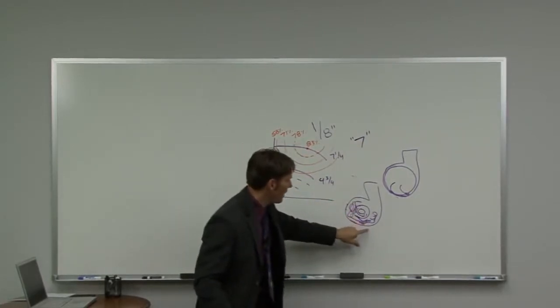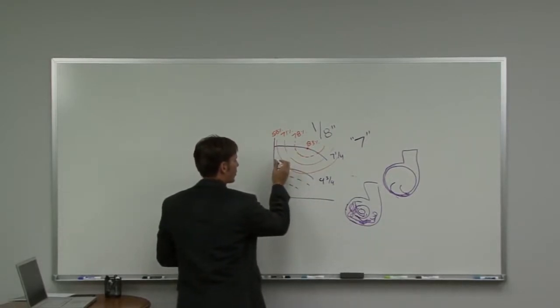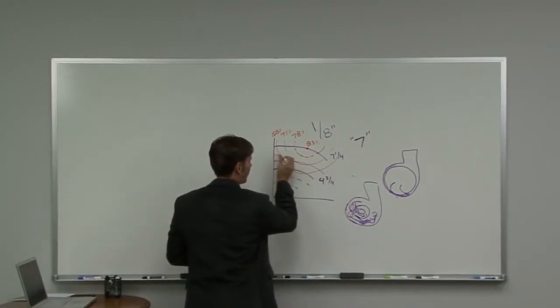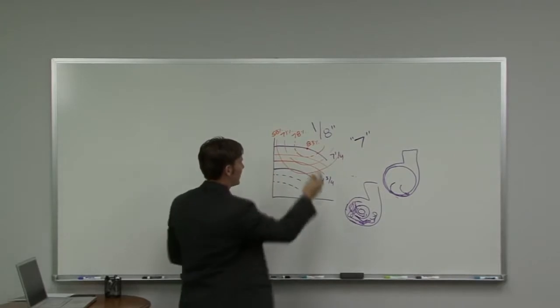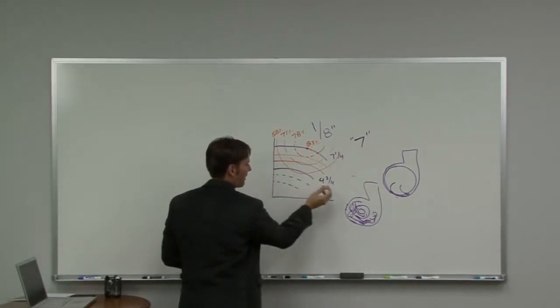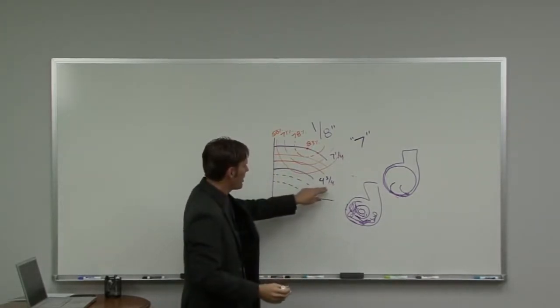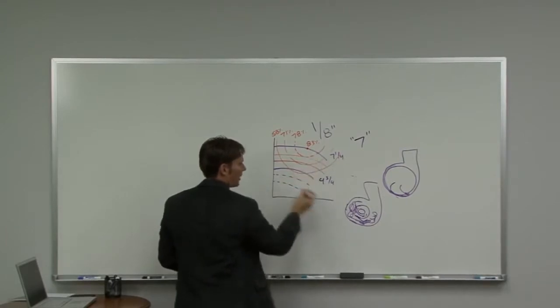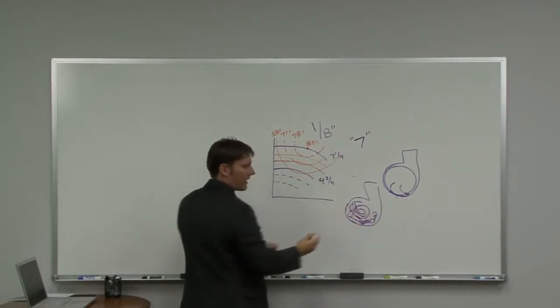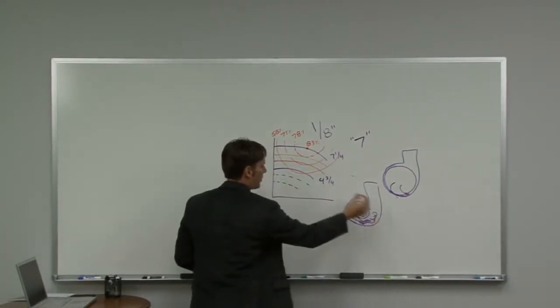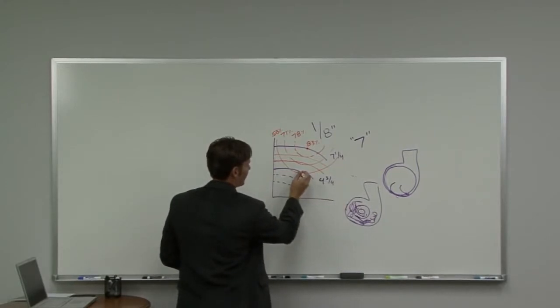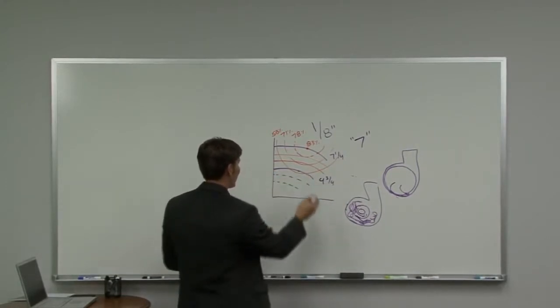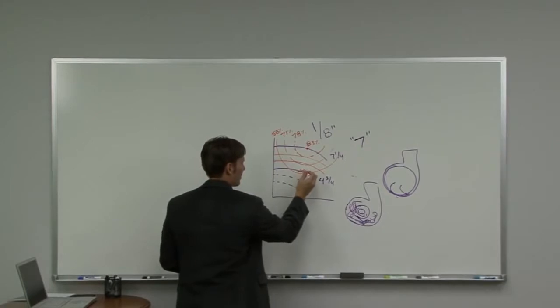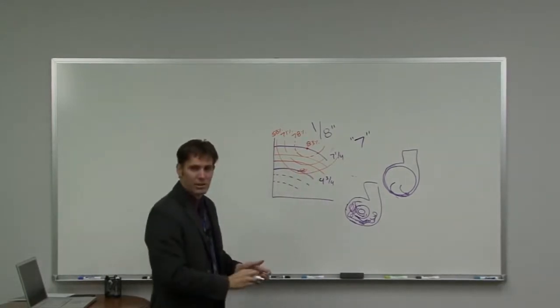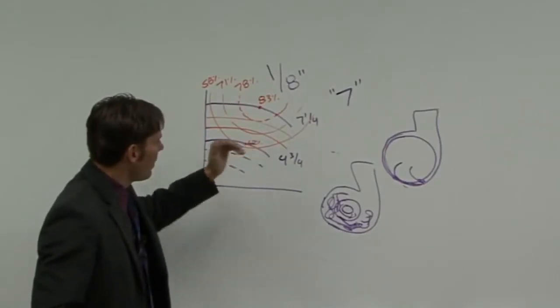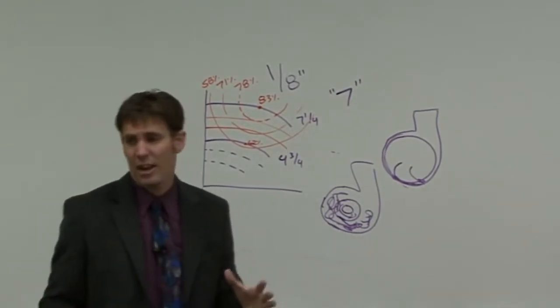Just like I mentioned down here, if I put in smaller pump curves, notice that I can no longer get to that point. If I'm down here with a 4 3/4 inch trim, my impeller has been cut down. I've taken all that metal off, and now I've got all those open spaces. The maximum efficiency I could be here is maybe 62% efficient. Not very efficient.